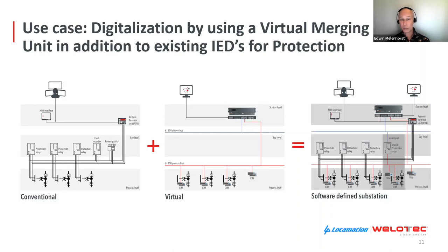The big difference with the initial substation is that network operators now have reliable and accurate process information, which will enable them to utilize the grid more effectively. Also, maintenance personnel and analysts can profit from all the measurement data that becomes available from the process bus. And remember, the original protection and control functions are still in place and untouched until you decide to replace them with state-of-the-art protection and control functionality running on the substation server.